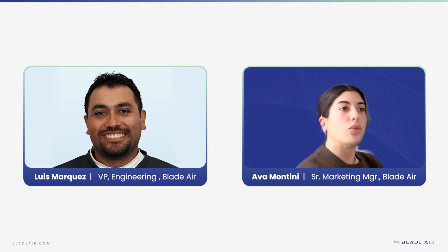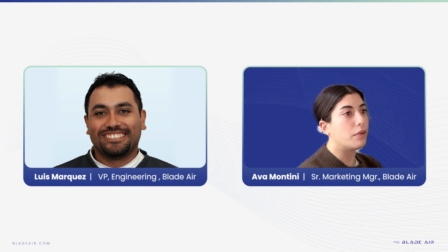At a Big Ten school, we have challenges with preventative maintenance in general and filter changes especially. It would be nice to see change in efficiency over two times the recommended filter change interval. If the electrostatic filter will handle extended change intervals, there may be additional savings, since they do not tend to reach the high pressure drops when loaded like pleated filters do.